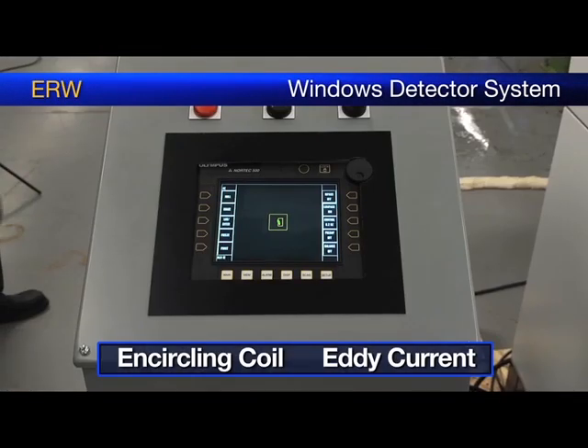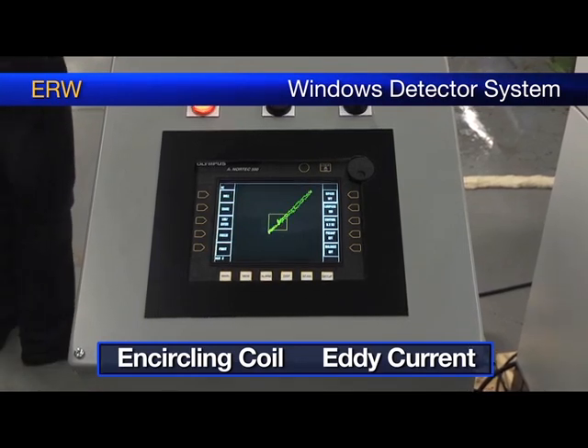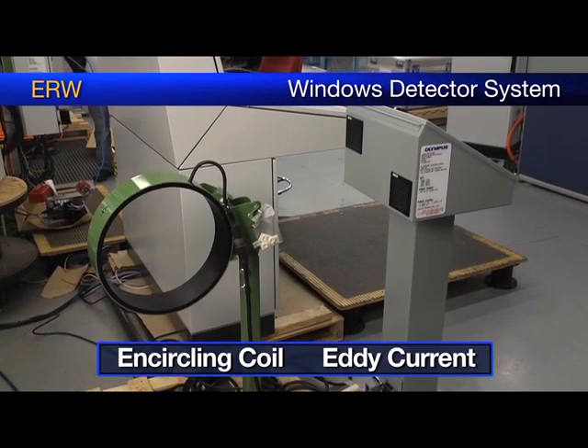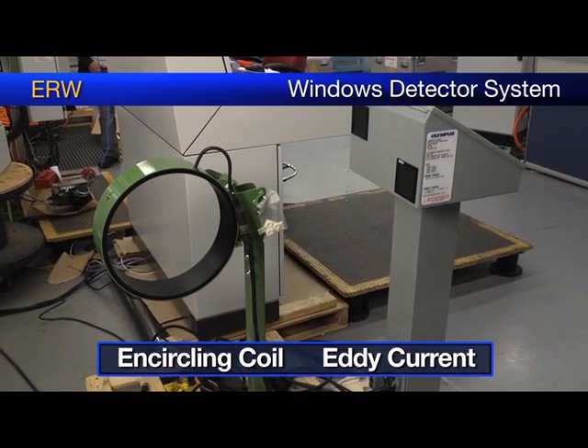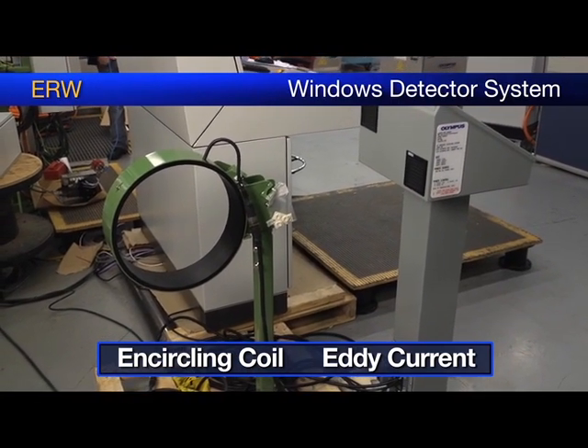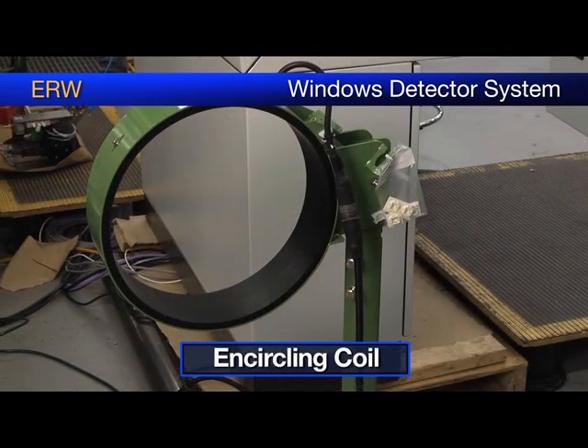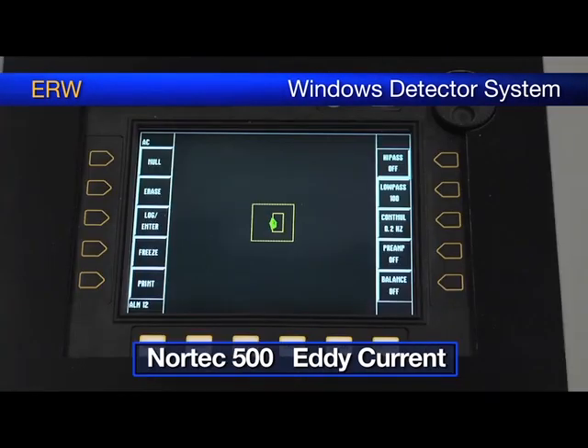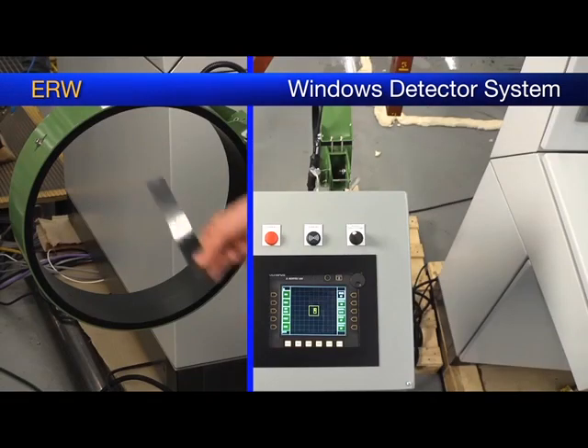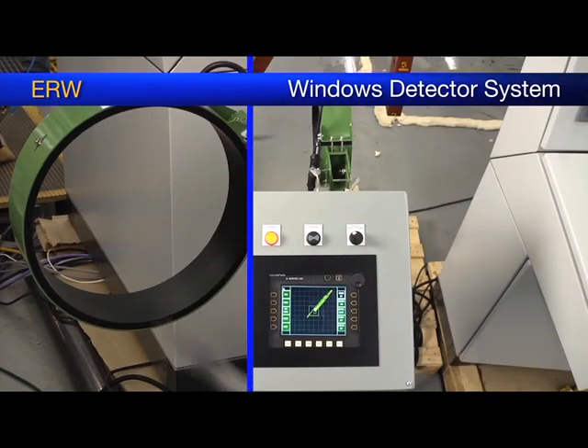For protecting the system, we use a combination of an encircling coil and an eddy current Nortec 500 instrument. This protection system is designed to detect openings on pipes that could damage the inspection probes. The coil is designed to detect the variations in the magnetic field created by the material variations coming, for example, from an opening on a pipe. Any magnetic field disturbance in the coil is going to generate an alarm that is going to be detected by the PLC, and it will trigger the raising of the inspection probes.